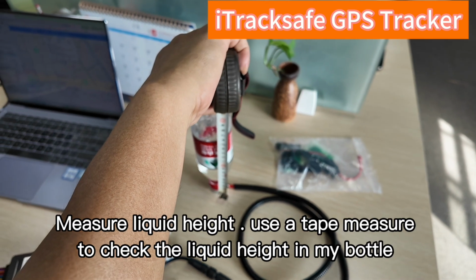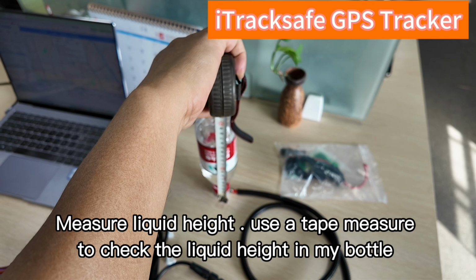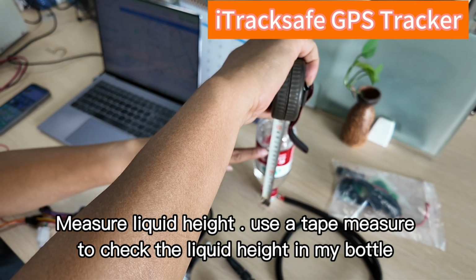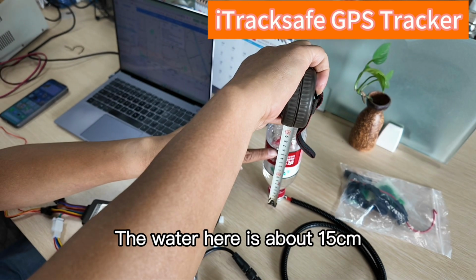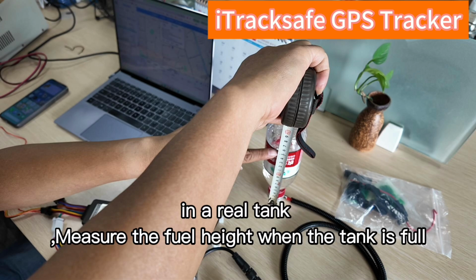3. Measure liquid height. Use a tape measure to check the liquid height. In my bottle, the water height is about 15 centimeters. In a real tank, measure the fuel height when the tank is full.